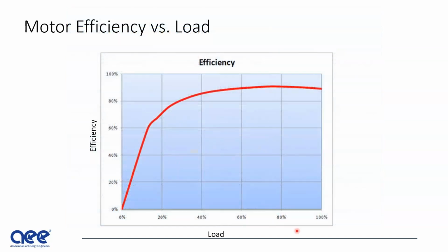Motor efficiency versus load. Motors are designed to be optimal for efficiency at around 80%. That's where most are loaded. When you get below 40%, the efficiency really drops off.